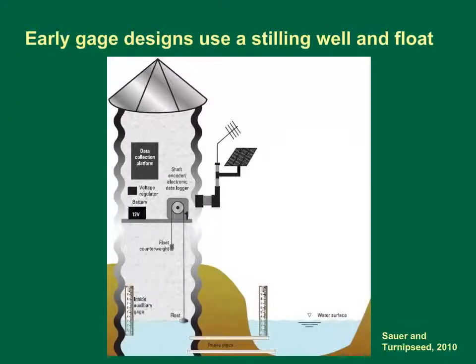This schematic diagram shows a stream gauge with a stilling well next to the stream. A float assembly is used to measure the distance from the pulley to the water surface in the stilling well. The stilling well is used to protect the float assembly and dampen surface flow oscillations. The stilling well is connected to the stream by multiple intake pipes. The objects that look like partially submerged rulers are staff gauges used to manually check the water level. Gauges with stilling wells have inside and outside staff gauges to ensure that the stilling well matches the river level. In this type of gauge, the float line is connected to a pulley that turns a shaft.